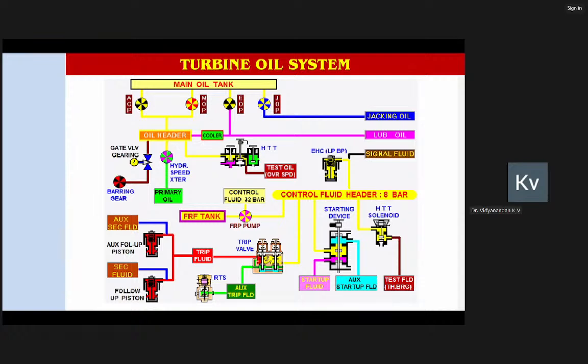But for 250 megawatt and above, ordinary lube oil is not used for the governing purpose. It is the control fluid, a fire-resistant fluid with an auto ignition temperature of more than 700 degrees Celsius. That is the fluid used for the governor. And in case of a typical 500 megawatt, both 8 bar and 32 bar pressure signals are there, whereas in case of 660 megawatt, only 50 bar signals are there. There is no 8 bar and no 32 bar in 660 megawatt.